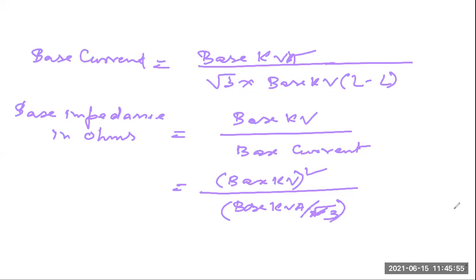Now next is the base impedance in ohm. Base impedance in ohm means base kV square by base MVA. This is basically what will happen: this is base kV square, and if you are considering this divided by 1000, this 1000 is multiplied here. So if you are dividing base kVA by 1000, this becomes base MVA. So basically this formula is that formula. Base impedance in ohm equals base kV square into 1000 by base kVA. So these are the two basic rules: base kV line to line square into 1000 by base kVA.